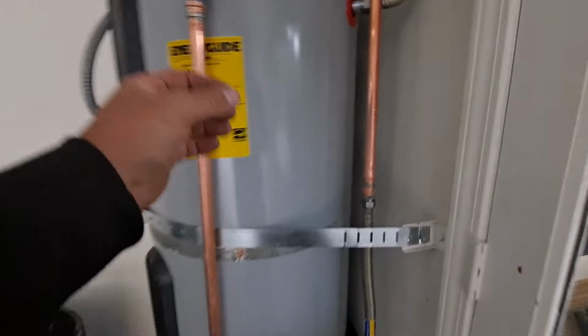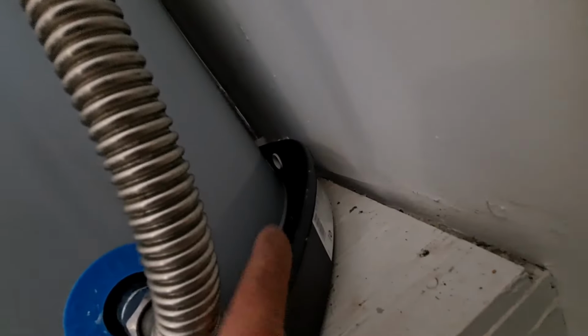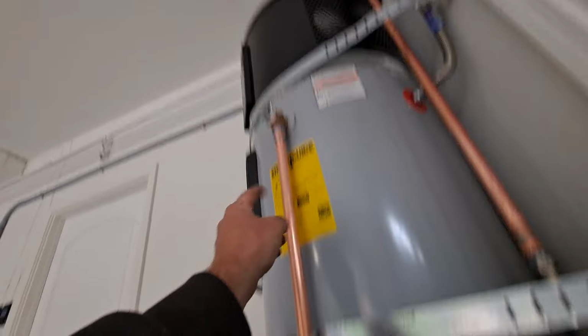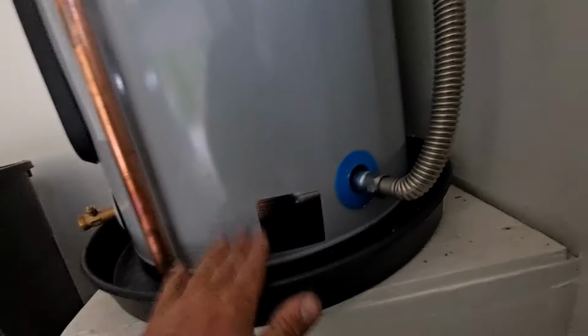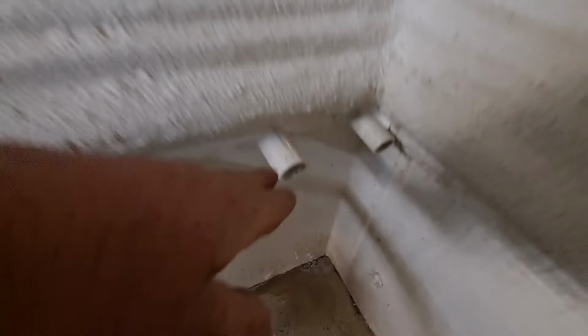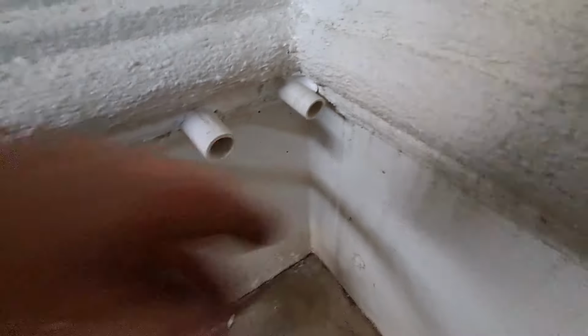I did make a couple decisions. One, down here on the pan, that goes out with a 1-inch. Behind it, there's an elbow and a 3/4 for the condensate drain. And because I already had made two big penetrations, I didn't want to make another one. I went ahead and took the relief valve here, dropped it into the pan, at which point it's going to go out there. So this is equivalent of a drain. I guess I got to fix the carpet, the turf here. But the two penetrations are here, sealed them all up. As you see, the condensate drain's already running, doing its thing.